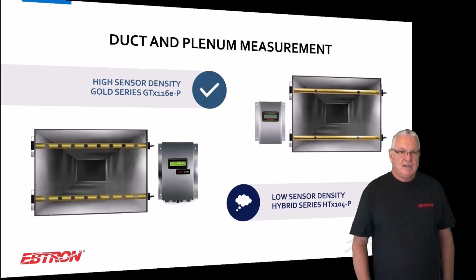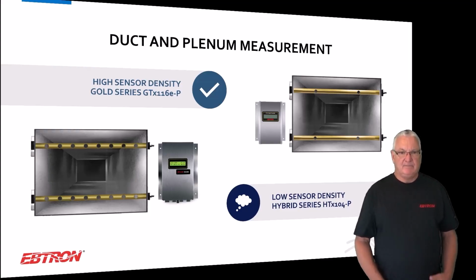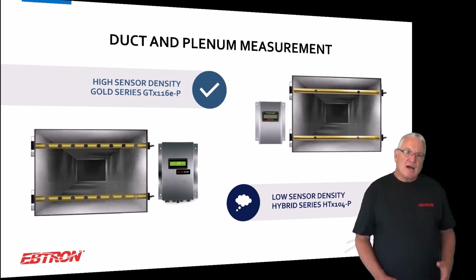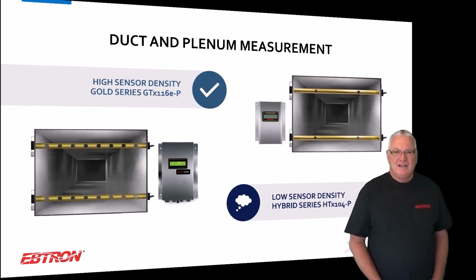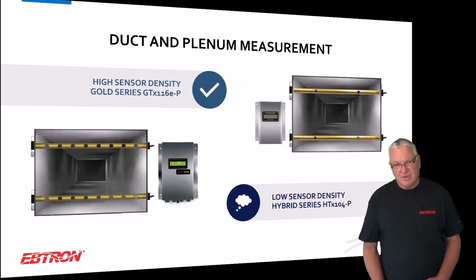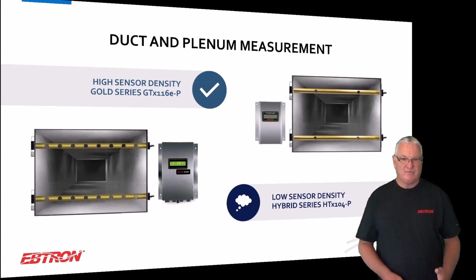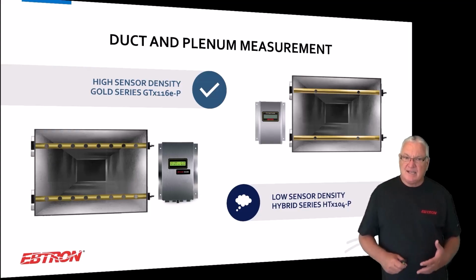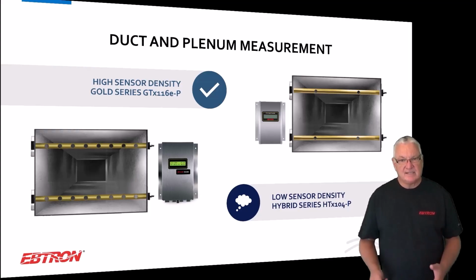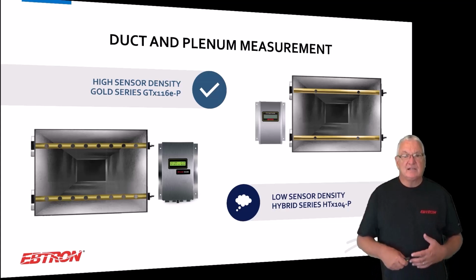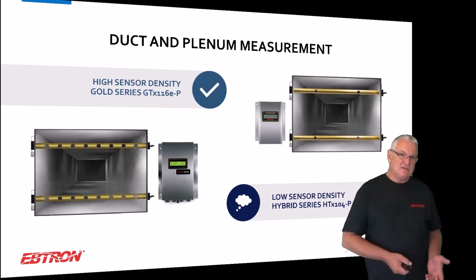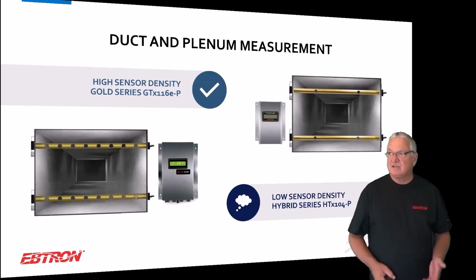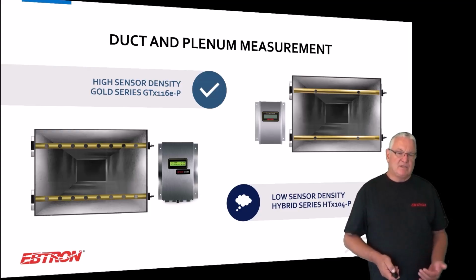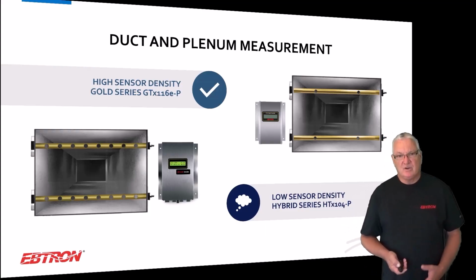We have our Gold Series. That's what we sell most of. High sensor density, most functionality. It's what I would apply on most of my larger duct systems. What's larger? I don't know, anything over 2 foot by 2 foot, maybe. Low sensor density stuff is pretty much very similar to the Gold Series under 2 foot by 2 foot in performance. But as the duct size gets larger, it has fewer sensors. Because it has fewer sensors, the installed accuracy uncertainty increases. It doesn't mean it's not going to be as good as a Gold Series, but the probability that it is not there increases because of velocity profiles, okay? But they're the same technology, same flow measurement technology. The Gold Series has more functionality.